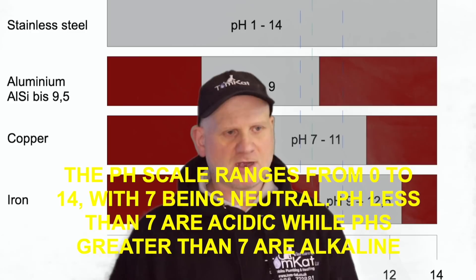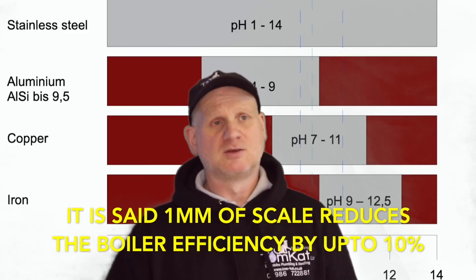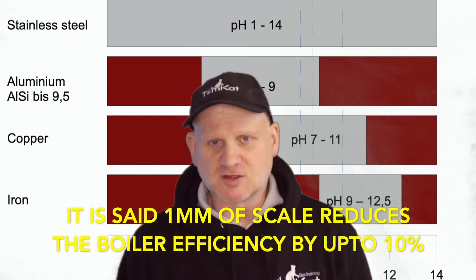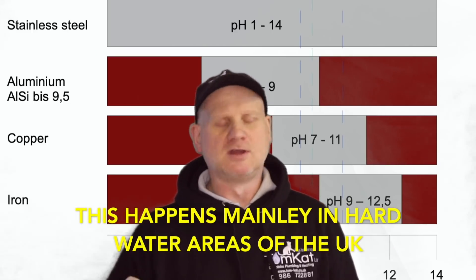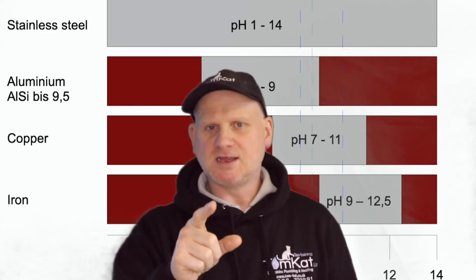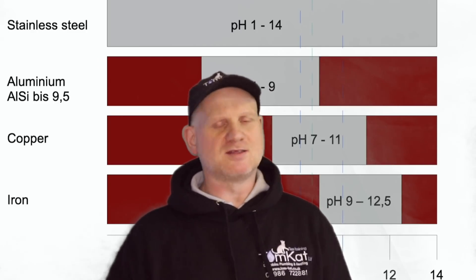Why is it important to check the quality of water in your central heating system? Two reasons: scale build-up and corrosion. Limescale is naturally in your water and can deposit onto boiler surfaces at temperatures over 60 degrees, insulating the boiler, reducing heat output and efficiency. Then there's magnetite and sludge circulating through the system.